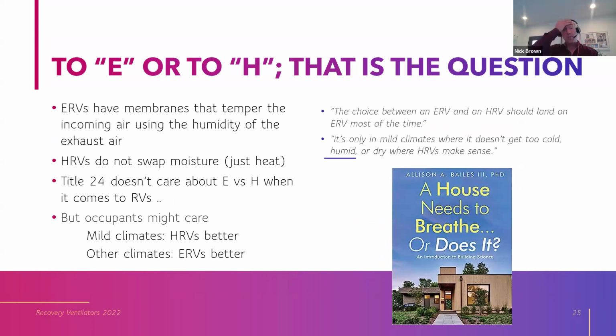Now, many of you may have come for this question. What's the difference between ERVs and HRVs, and which one's right for me? First, the difference. ERVs, energy recovery ventilators, enthalpy recovery ventilators, if you want to be a little more building scientist about it, have membranes in that heat exchanger core that allow moisture to flow through them in the air, water vapor. Whereas heat recovery ventilators do not. They just swap heat. So ERVs swap heat and moisture. HRVs just heat.